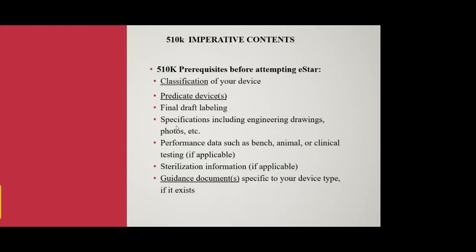These are prerequisites that you must have. You can easily download eSTAR now from the FDA website, and I'll show you the link later on. It's merely a PDF template. It's an XFA type, secured with a digital certificate issued by the FDA, so you can't edit or muck with it. And I have a slide to show the error message that happens when you attempt to do that. But the point is, for any device submitter, by the time you get to eSTAR, you ought to have all these collected, compiled, verified, assembled, and so on. So eSTAR is not a magic wand. It will not do all the work for you that leads up to the submission. It is a construction template, okay, versus a submission template.